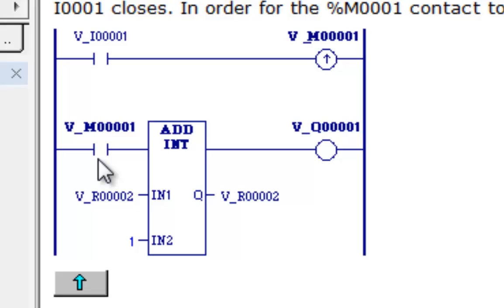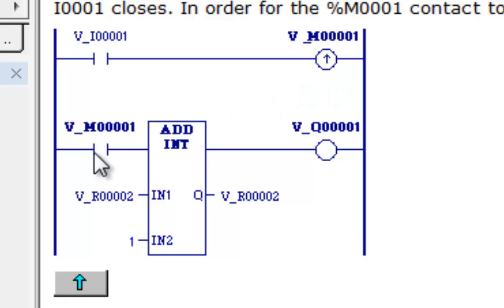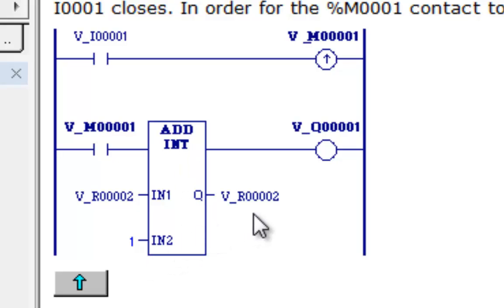Now, with this new setup here, your push button would be coming on input one. It would cause this transition coil, the one-shot coil, to go on for only one scan. These contacts would close for one scan. And the add-int would only add one to the register two. So let's go see how this works.